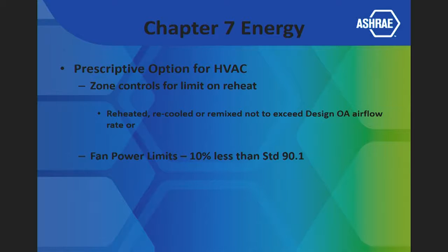Which means the designers now have to think a little bit differently. One of the ways to do that is to make the equipment a little bigger, make the ductwork a little bigger, so it doesn't take as much energy to move that air. Think about this. If you had two straws, and you're drinking with them: with a really skinny straw versus a fat straw, you don't have to suck very hard. With the skinny straw, you're going to suck your brains out to get something to drink. That's to do with pressure loss.